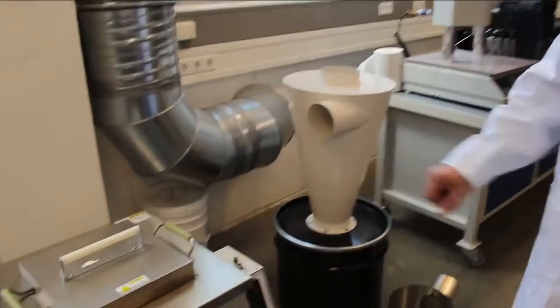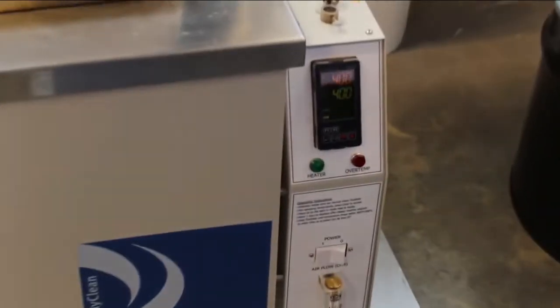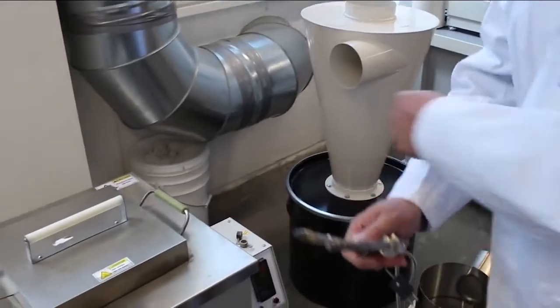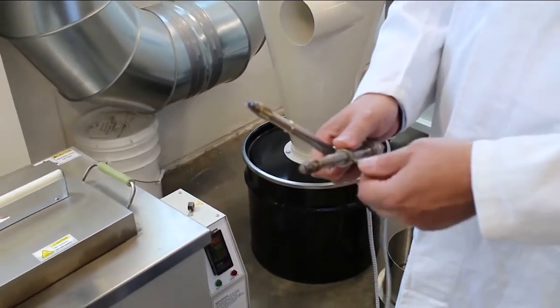So now time for the demo. I have set up the Polyclean at 400 degrees C for pressure sensors and we are going to clean them for about 8 minutes. So first thing I will put the stoppers to prevent the sensors from falling down completely inside the bath.